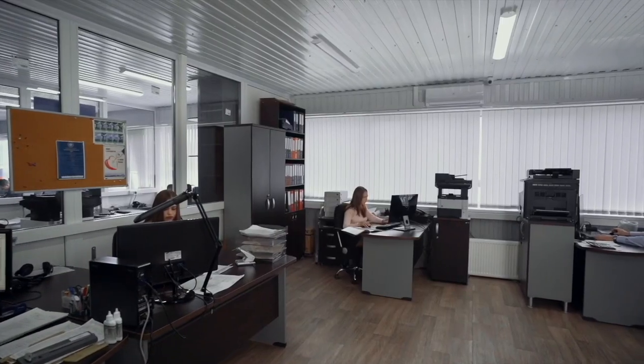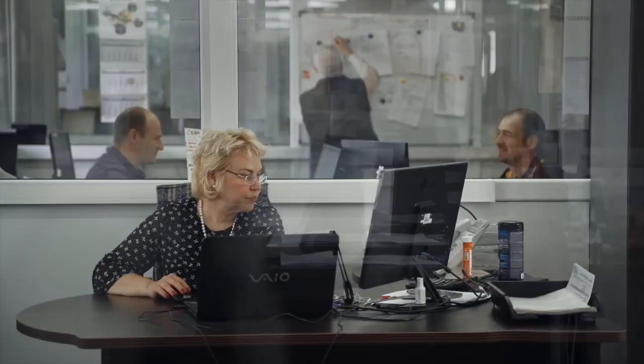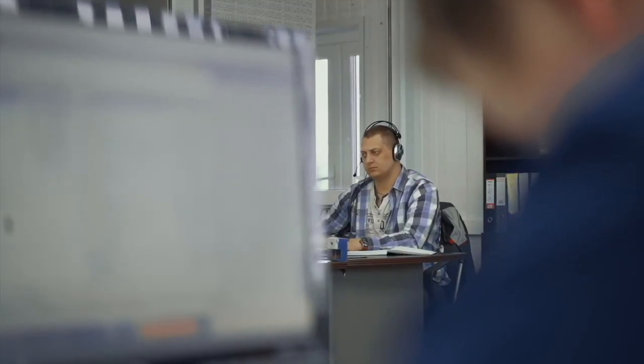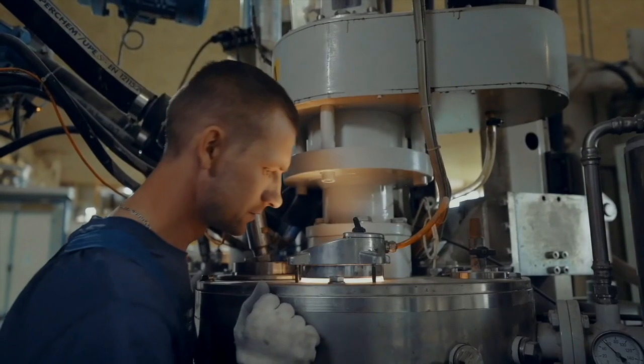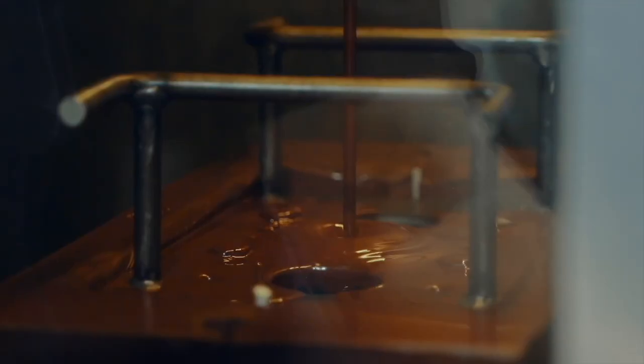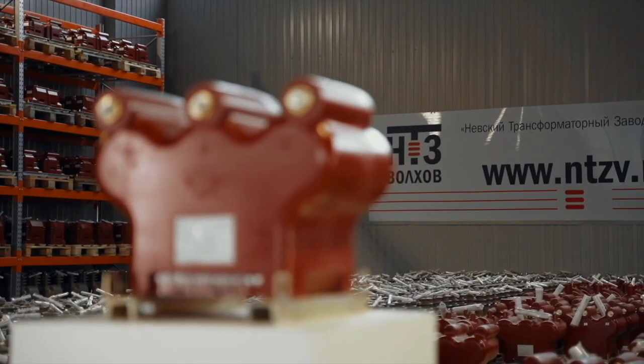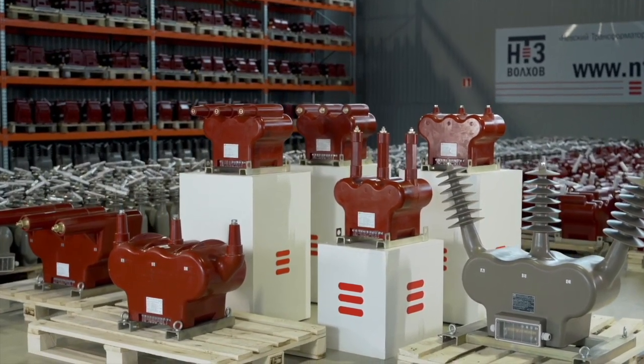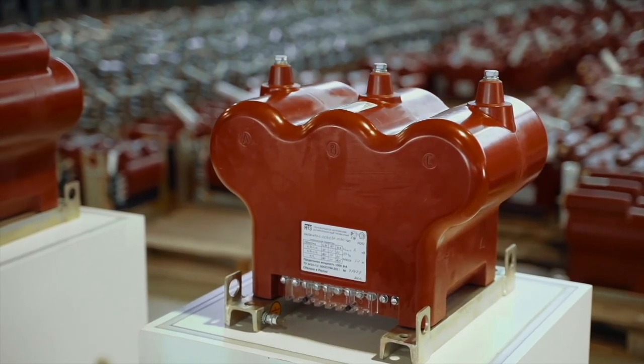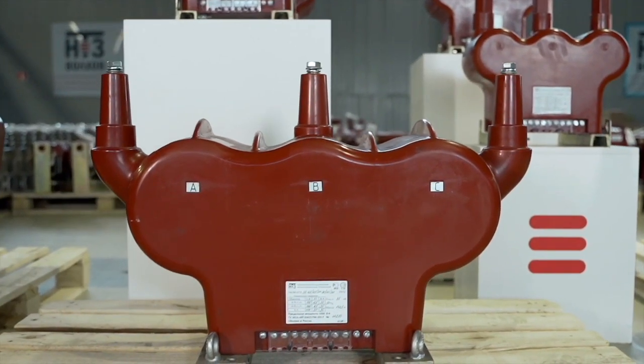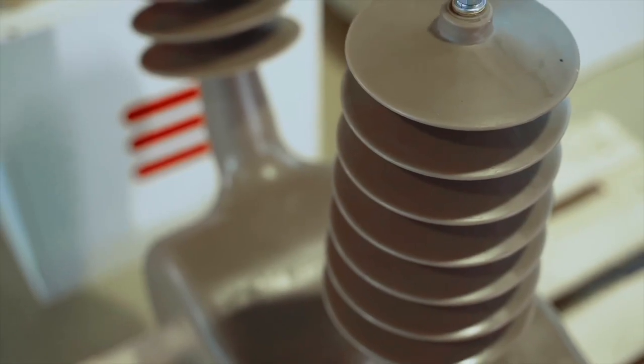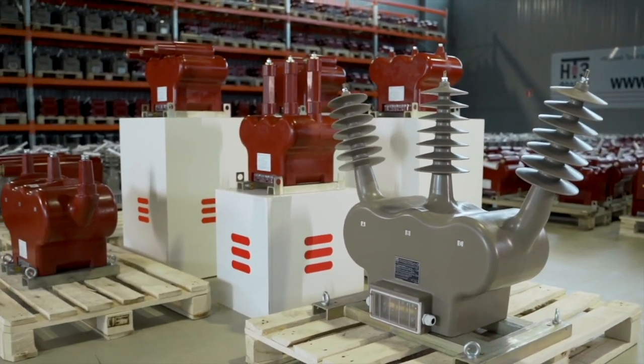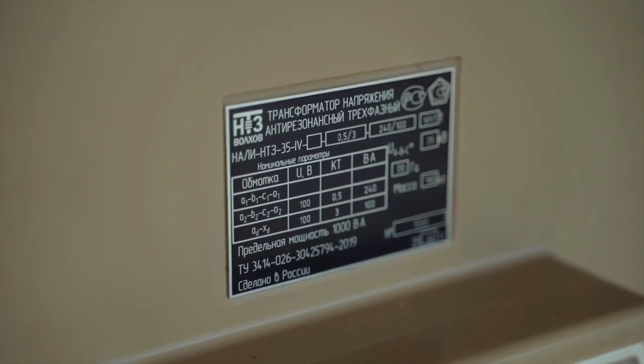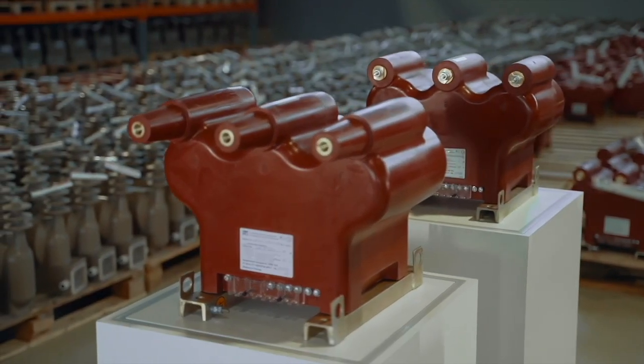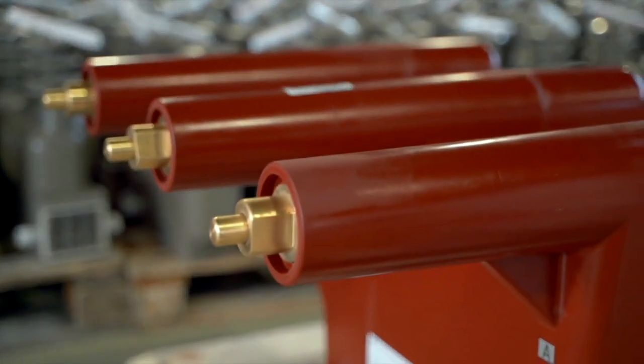The NTZ Volkhov team carried out numerous researches and developments and created a three-phase voltage transformer of increased stability in a single case made of epoxy compound. These are anti-resonance three-phase voltage transformers NALI-NTZ. The transformer of the NALI-NTZ series, in addition to all its characteristics, is completely protected against the ferroresonance effect. This transformer is not only capable of transmitting a measuring signal, but also serves to control the occurrence of single-phase earth faults for 6 to 35 kV networks, thus it fully implements all the functions of traditional voltage transformers, while completely eliminating failure during operation.